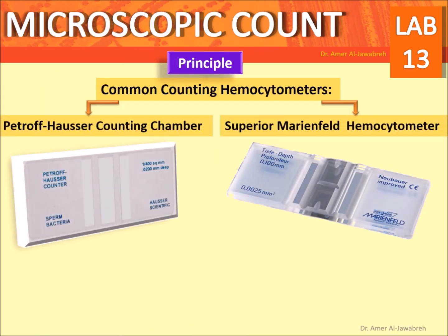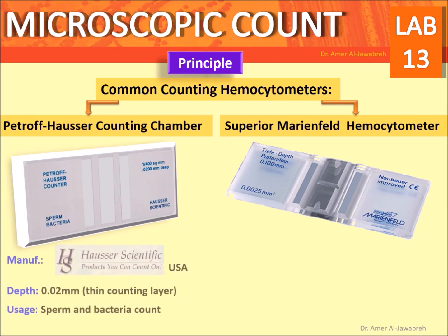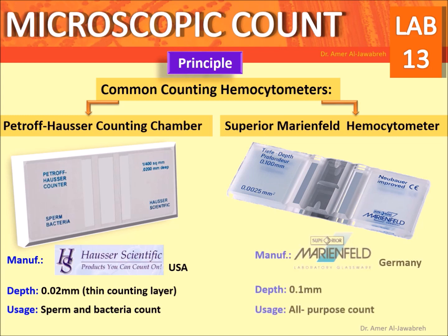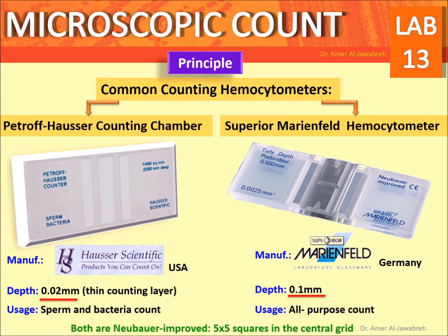Common counting hemocytometers include the Petroff-Hauser counting chamber and the Superior Marienfeld hemocytometer. The Petroff-Hauser is manufactured by Hauser Scientific, USA, and has a depth of 0.02 mm — a thin counting layer used for sperm and bacterial counts. The Marienfeld hemocytometer is manufactured in Germany, has a depth of 0.1 mm, and is used for all-purpose counting. Both are Neubauer improved designs.